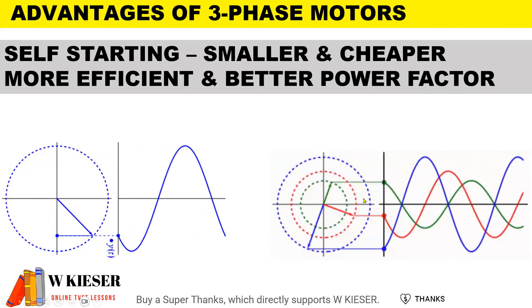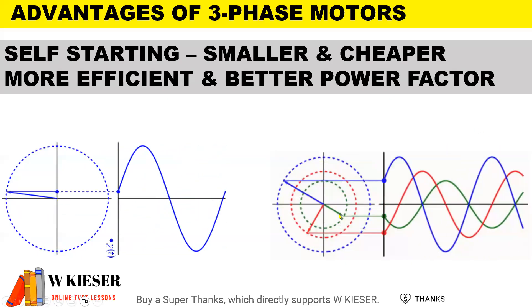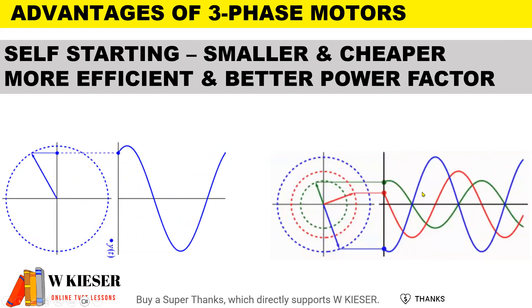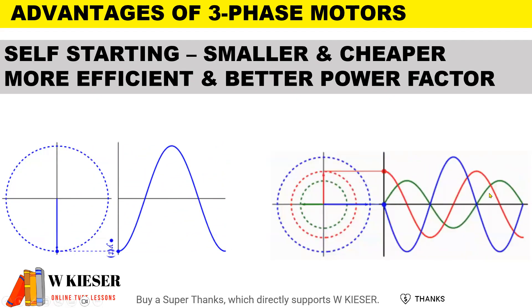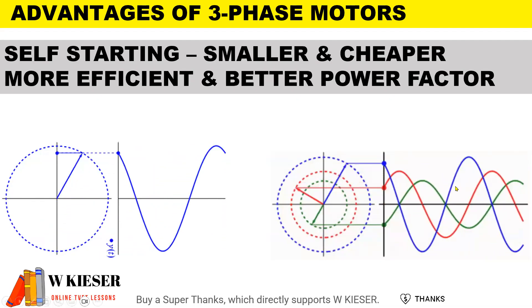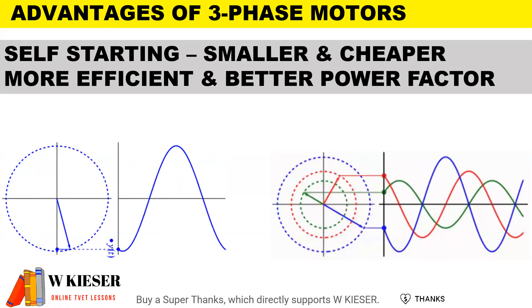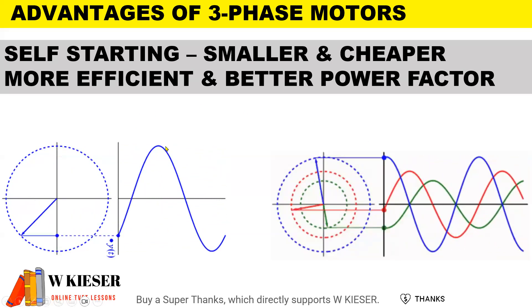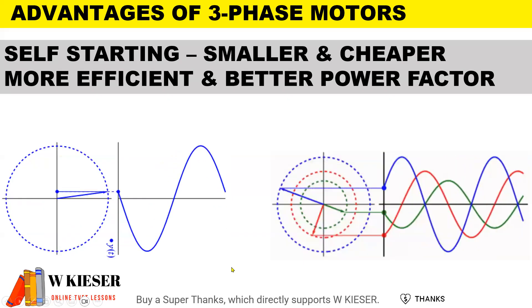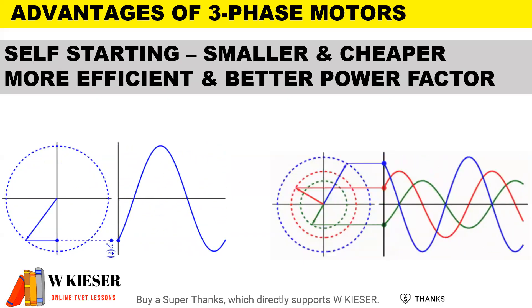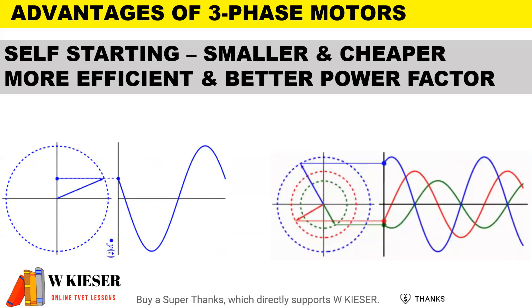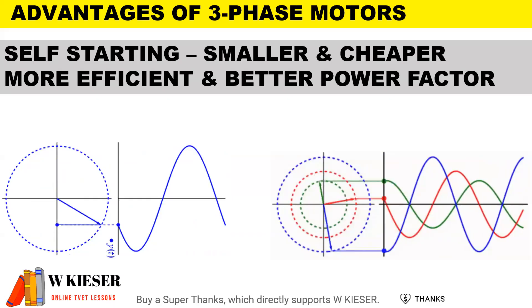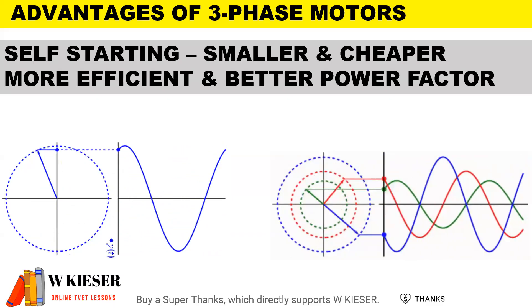A three-phase motor has three coils placed 120 degrees apart. As they rotate 360 degrees, they produce three sine waves. Because of the phase difference between the sine waves, three-phase motors are self-starting. However, a single-phase motor only produces one sine wave, and the problem is that single-phase motors are not self-starting. Three-phase motors are also smaller, cheaper, more efficient, and have a better power factor.